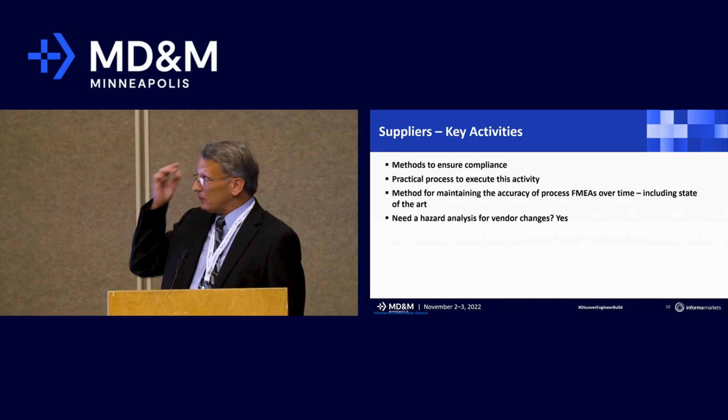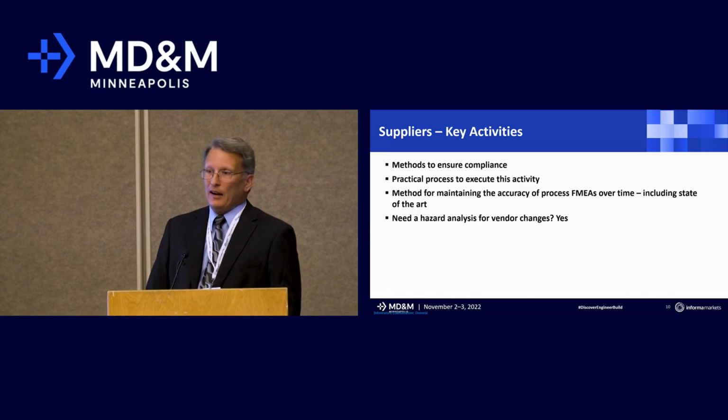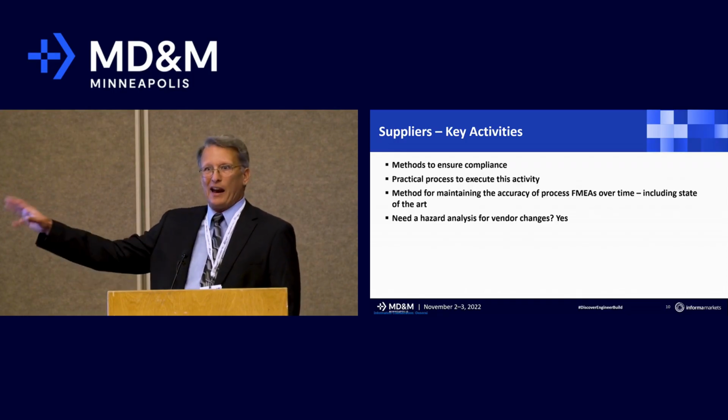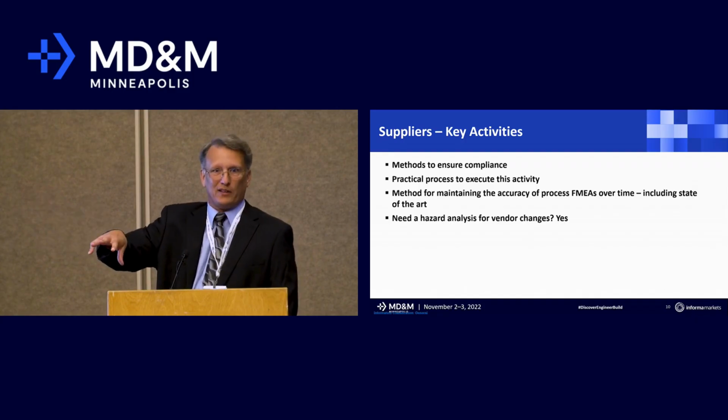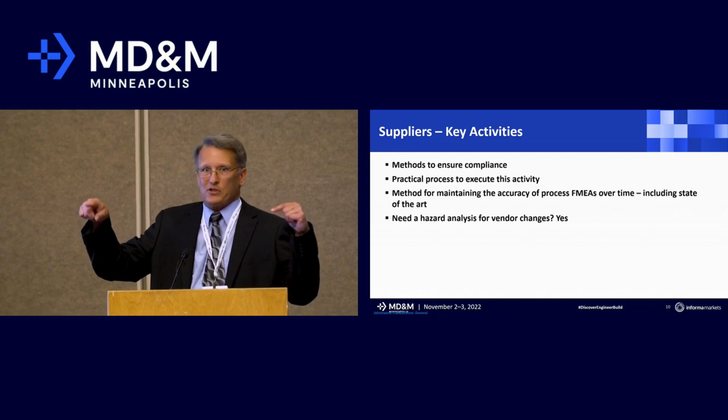And this last bullet is something I was actually asked by a client as I was putting these slides together, so I figured it's a great thing to add to this particular slide. It says, do we need a hazard analysis for vendor changes? And I looked at him and I paused for a few seconds. I just said, yes. He says, well, what if it's not a big deal? Well, you probably know it's not a big deal because you already have one. And so you can go back and look at the hazard analysis and say, it's not a big deal because it already is covered on line item 17.